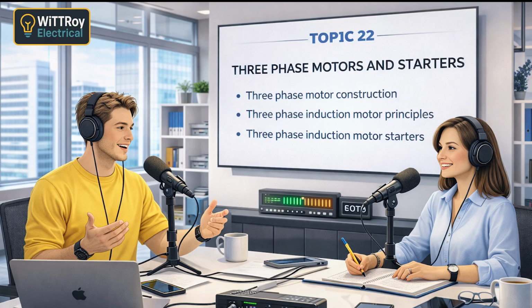Okay. Now, let's move on to direct online starters. The simple ones. Yes, a DOL starter connects the motor directly to full line voltage when the contactor closes. So no reduction at all. Correct. That means high starting current, typically 5 to 8 times full load current. That's pretty big. It is. The advantages are that the design is simple, reliable, low cost, and easy to maintain, with strong starting torque. And the downsides? Very high starting current, mechanical shock, voltage dips on weak supplies, and it's not suitable for large motors. So mostly small motors. Yes, fans, small pumps, workshop machines, small compressors.